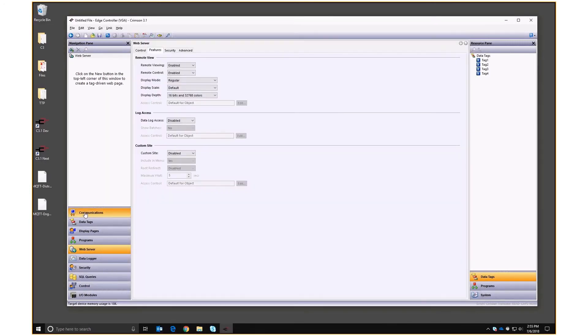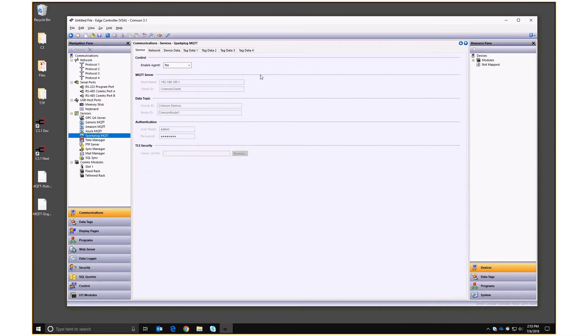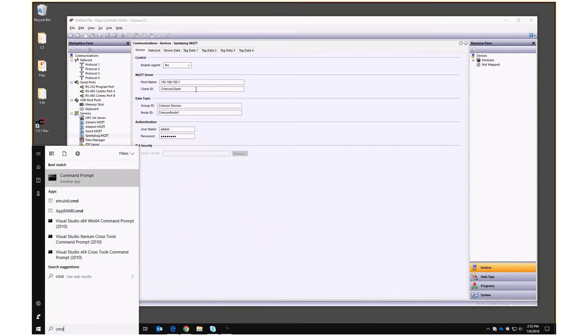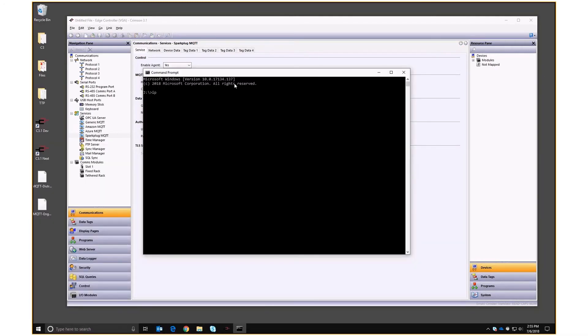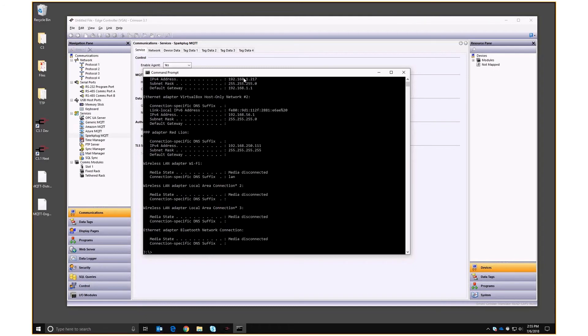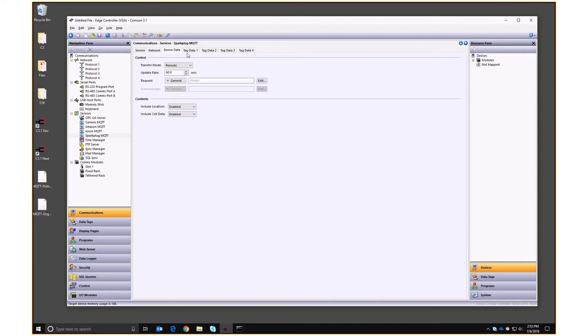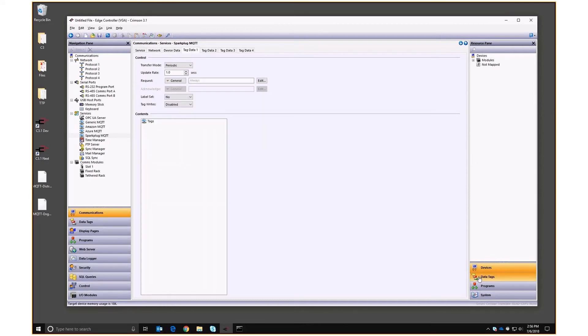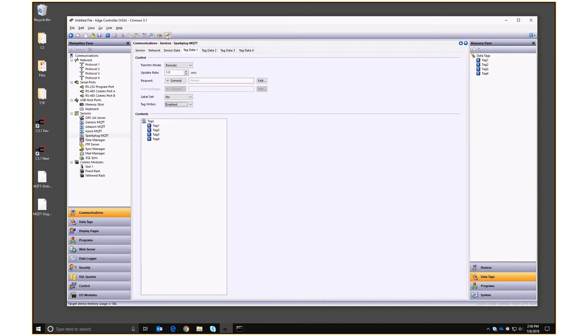Now let's go back into Communications, and here is our SparkPlug MQTT connector. Not a lot to do — we enable the agent, and we need to know the IP address or hostname of the device we're talking to. In this case it's on the local PC, so let's use ipconfig — it's 192.168.1.217. We download that, leave network settings at default, and under tag data we drag those tags across, enable writes, and download.